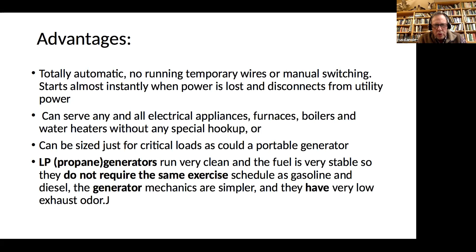You probably, again, don't need to run your clothes dryer, and maybe you don't need to run your electric oven at those times when you're on backup power. LP generators, propane, run very clean, and the fuel is very stable, so they do not require the same exercise schedule as gasoline and diesel. The generator mechanics are simpler, and they have a very low exhaust odor. I think you've probably heard that trucks that run on propane power run a lot cleaner. There's a lot greater distance between oil changes and that sort of thing.